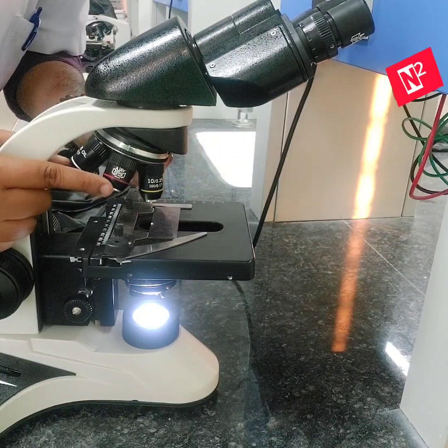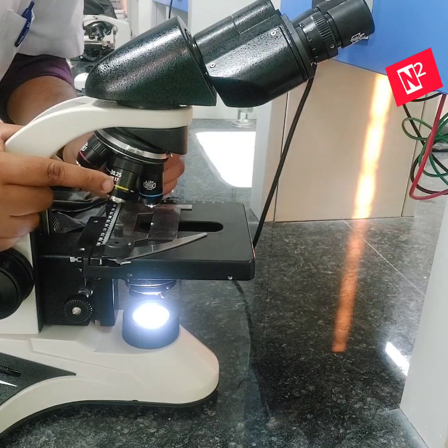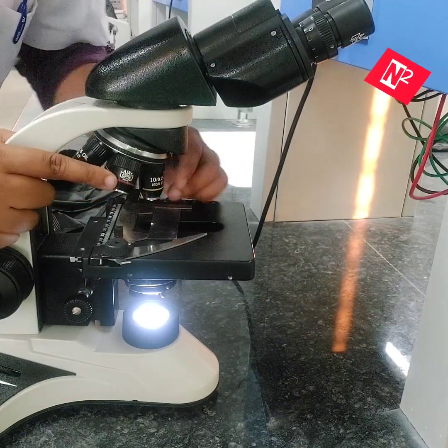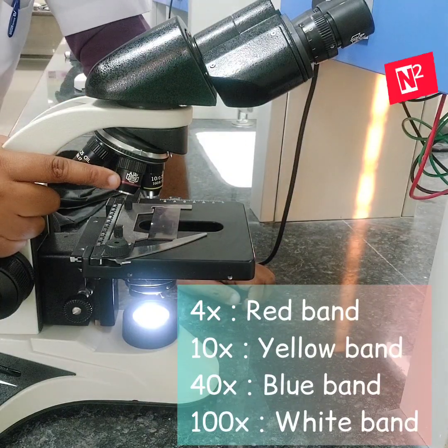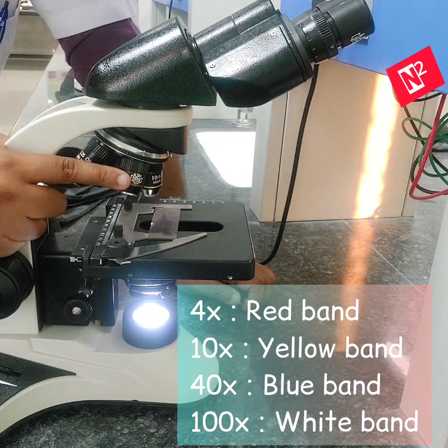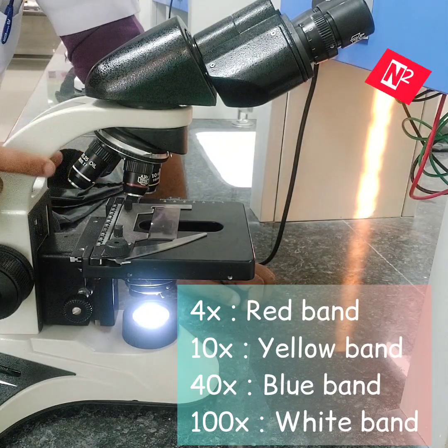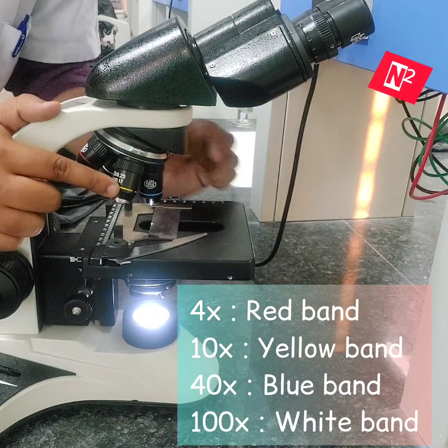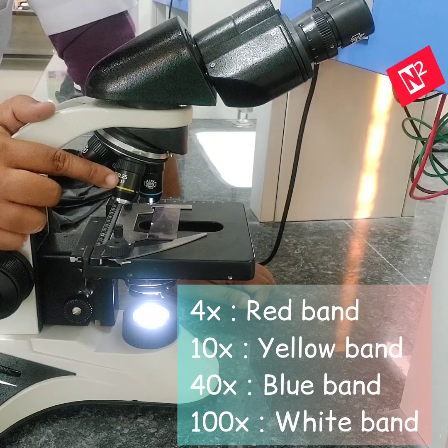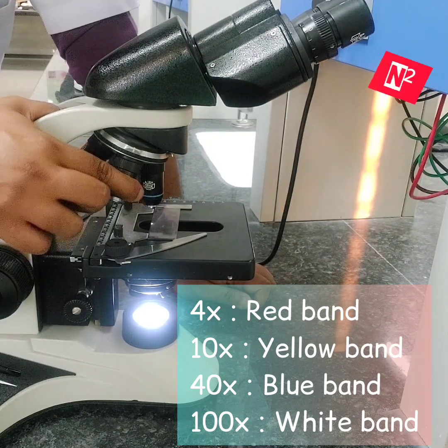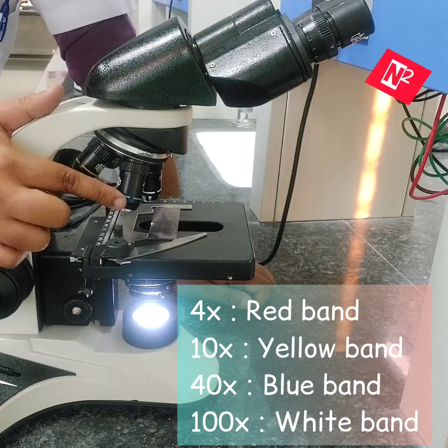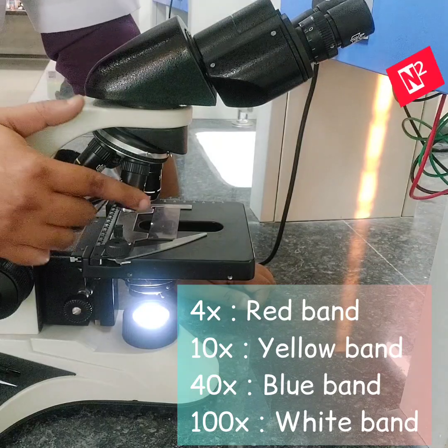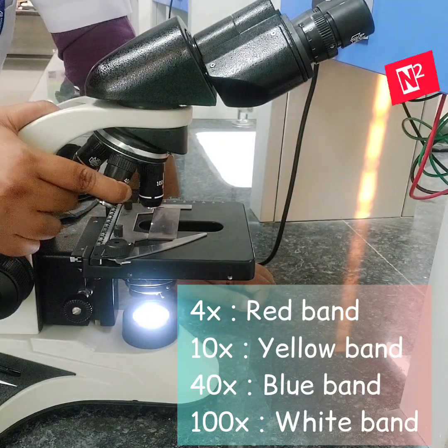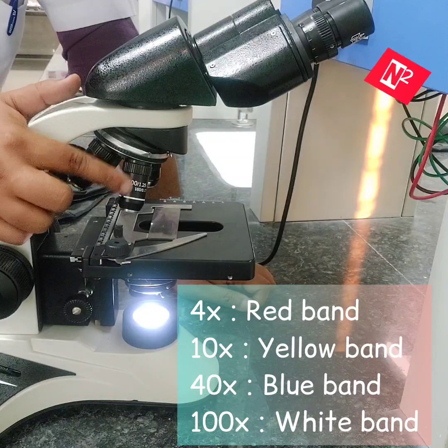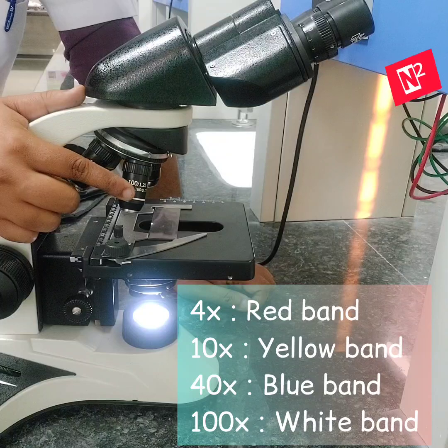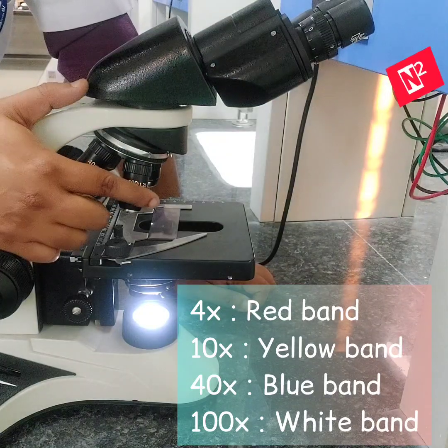You can also see the lenses are painted with some colors. The shortest objective lens has a power of 4x. It magnifies the object 4 times, and it's painted red. A little bit longer than this is the 10x power, painted with yellow color. A little bit longer than this 10x is the 40x power. It magnifies the object 40 times and it's painted blue. And the longest objective lens has a power of 100x. It is also called the oil immersion lens and is painted with a white band.